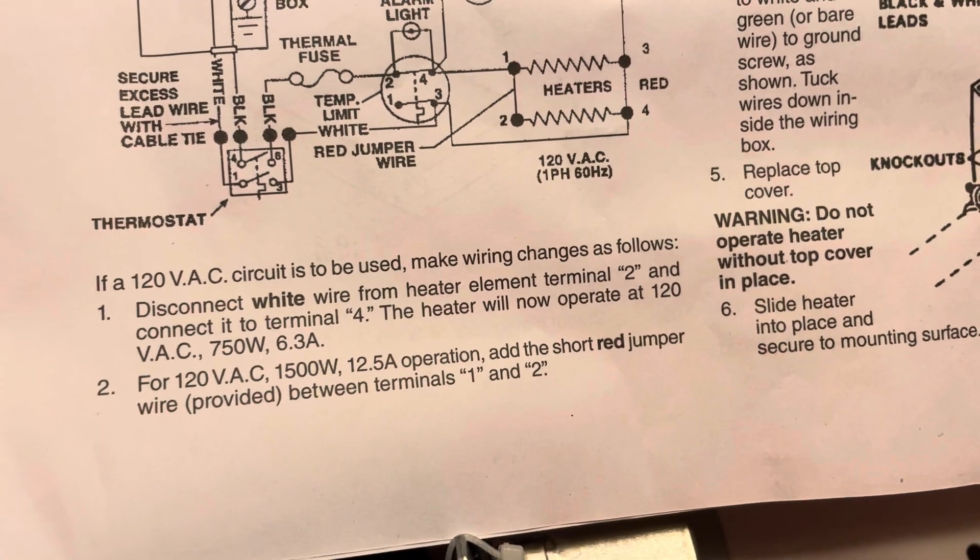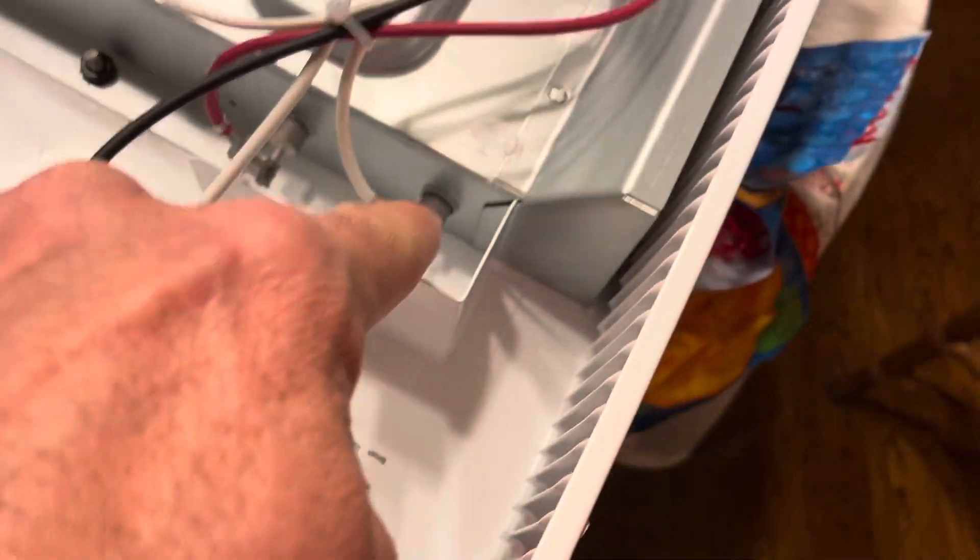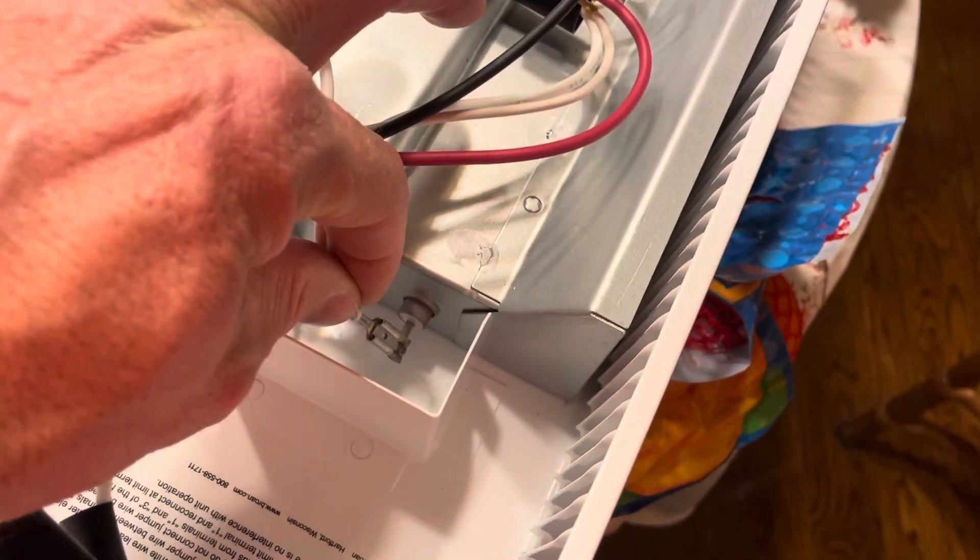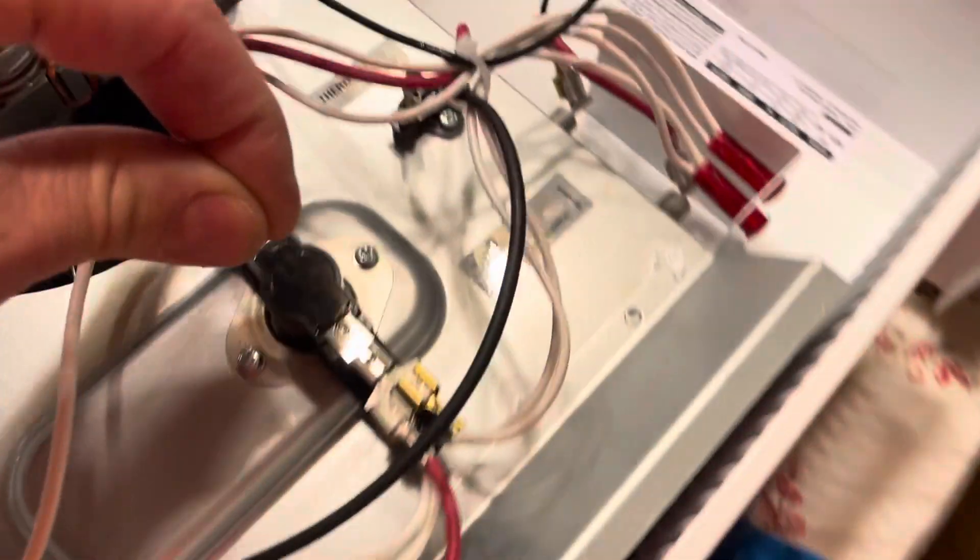And what is it telling us? It's telling us to disconnect the white wire from number 2 and connect it to terminal number 4. So here's terminal 2, we are going to disconnect this white wire from terminal 2, pull it out, we're going to bring it over to this side and they left an extra connection down here on terminal 4.